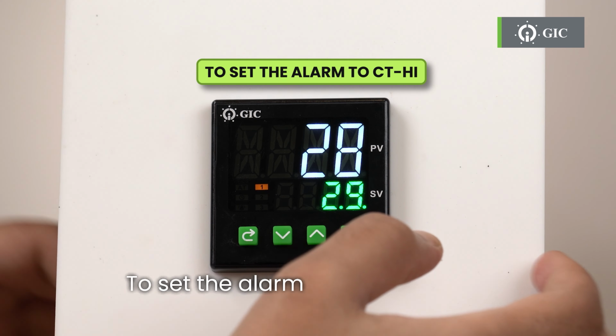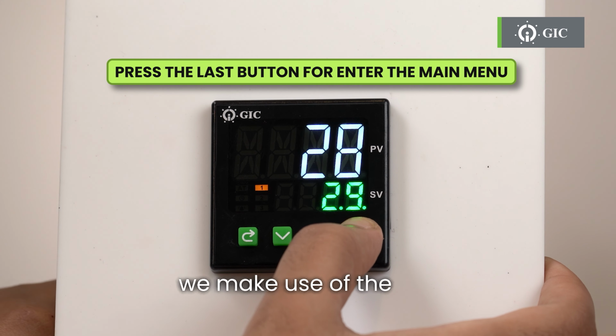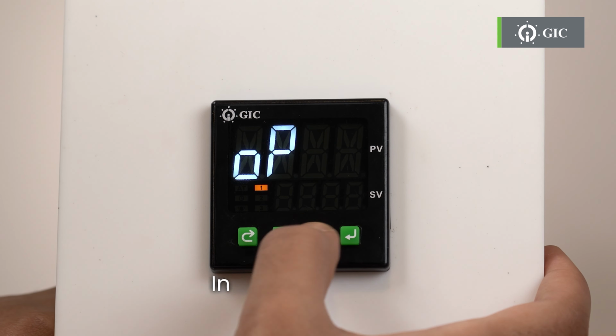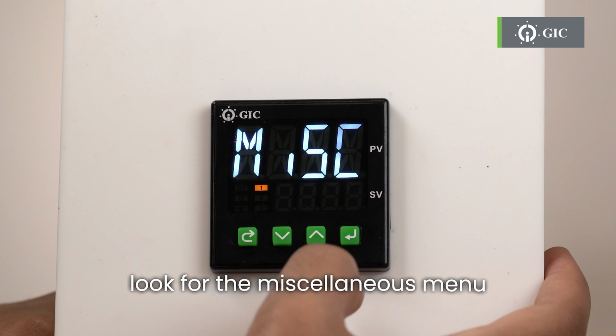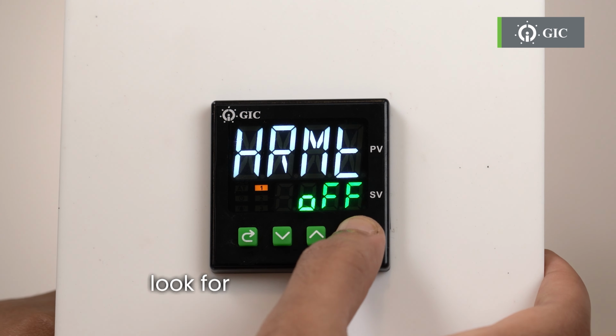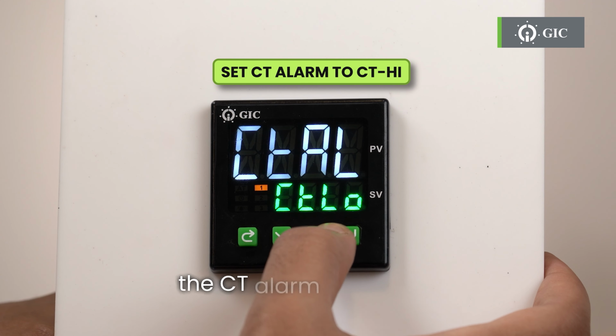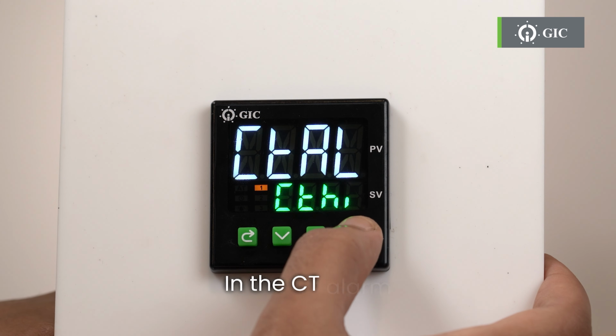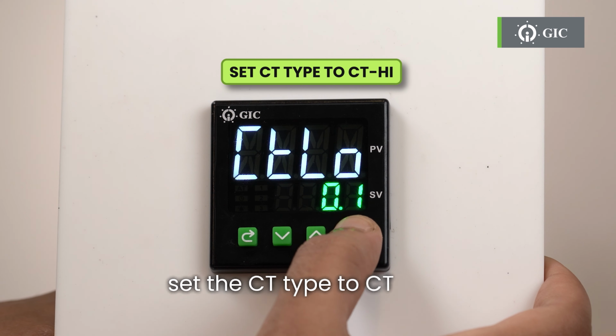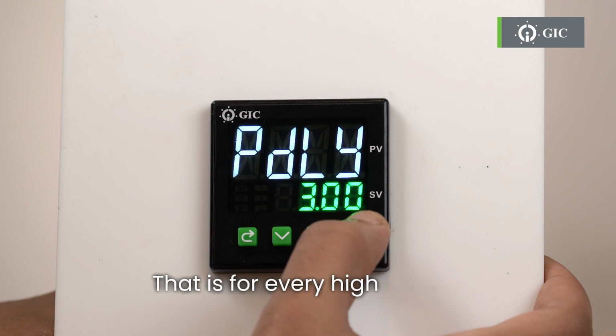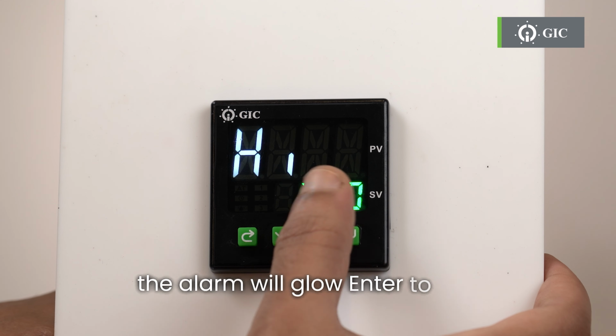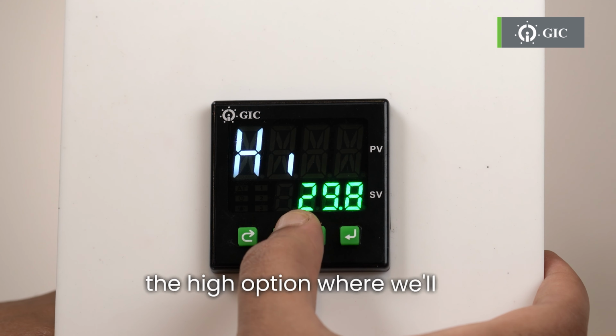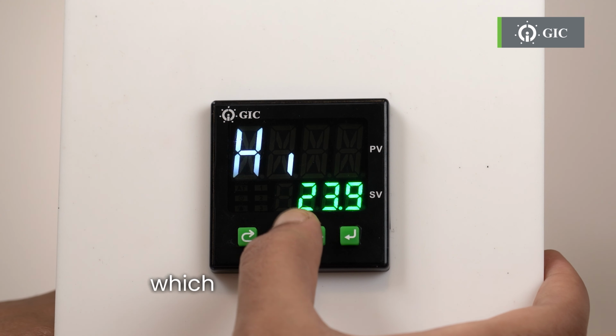To set the alarm for high currents, we make use of the last button and enter the main menu. In the main menu, look for the miscellaneous menu. Inside the miscellaneous menu, look for the CT alarm and set the CT alarm at CTHi. In the CT alarm, set the CT type to CTHi, that is, for every high current, the alarm will glow. Enter to find the high option, where we'll be setting the highest current above which the alarm should glow.